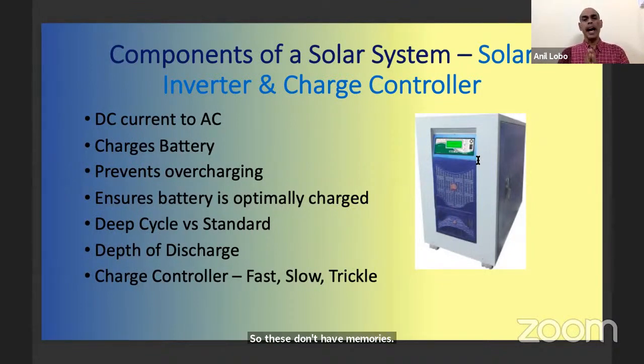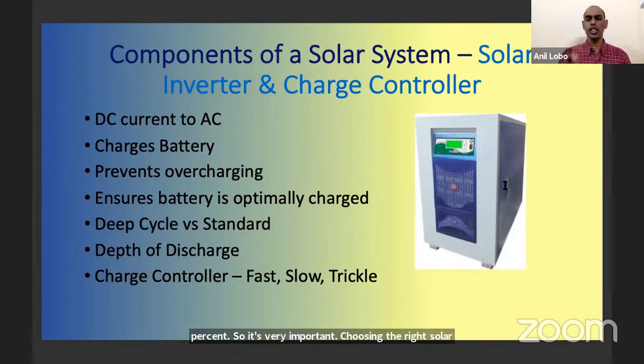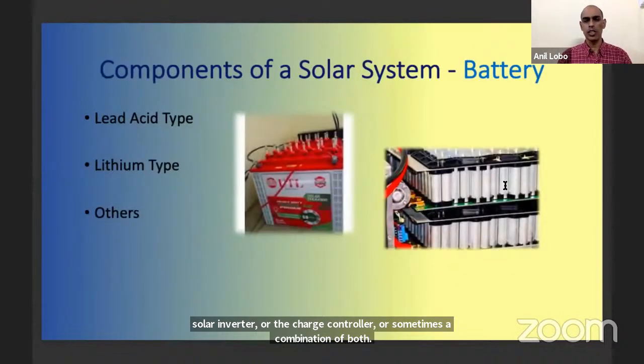Now your charge controller has to be a proper charge controller, and that is why some companies, especially some solar integrators, use a battery management system. Because in a battery management system, your charge controller will start by charging the battery really fast till it reaches about 80-85% capacity. Then it goes to a slow charge. A slow charge battery will charge at a much slower rate, over a little longer period of time. And then when it reaches 99% or 98%, it will give a trickle charge. That is, it will maintain it at 100%. So it's very important choosing the right solar inverter or the charge controller, or sometimes a combination of both into a power conditioning unit, or a PCU as it's called.